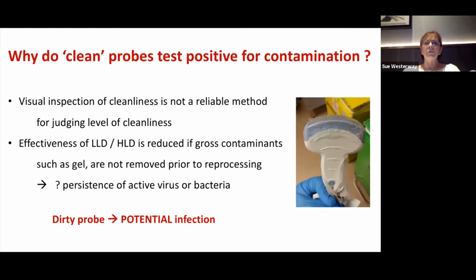Why do clean probes test positive for contaminants? Visual inspection of cleanliness is not a reliable method. The effectiveness of low and high level disinfectant is reduced if those gross contaminants such as gel are not removed prior to reprocessing. It can leave a persistence of active virus or bacteria, and a dirty probe can give the potential for transmission of infection.